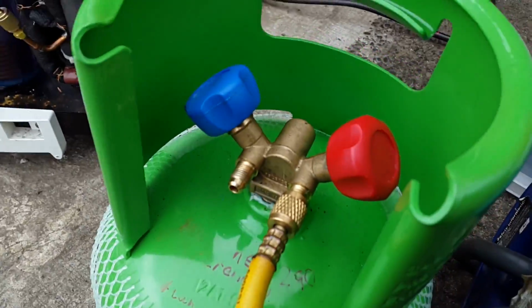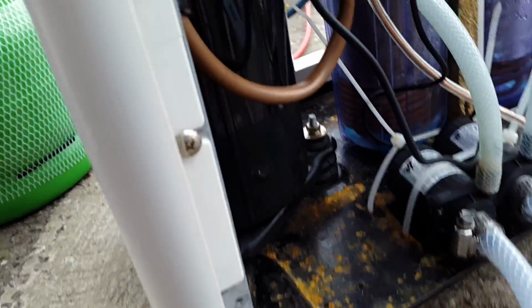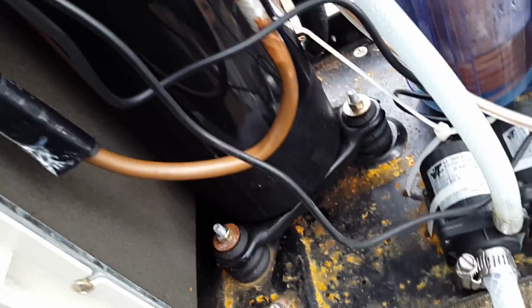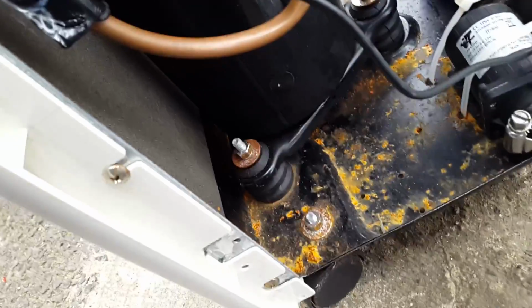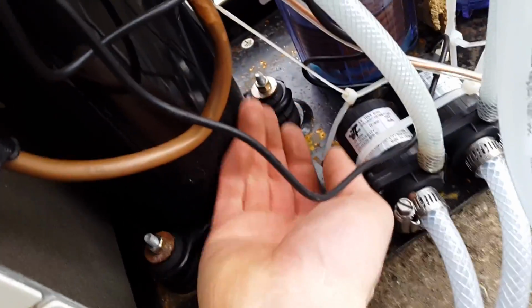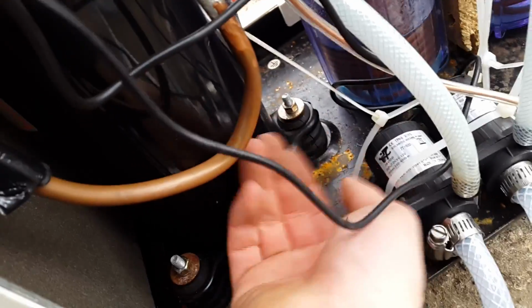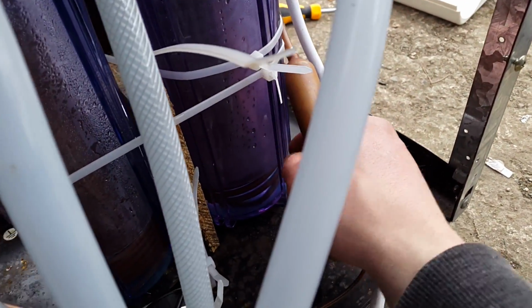So I stopped for a little while, no liquid came out the vapour side, so it's not full to the brim just yet. As you can see, the compressor's got this ring of condensation on the bottom, so it must have been sitting there like a tank of propane, and all the propane in the bottom of the compressor has evaporated off. It's all in the filter dryer as well, naturally cooled.